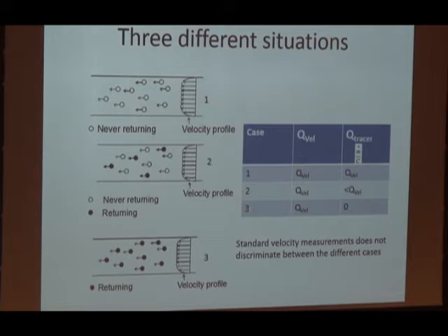If I then jump to the third case, when everything is coming back, then the tracer gas method gives an answer that the flow rate is 0. Because everything is coming back, how much gas I inject is fixed, but the concentration increases, so it becomes infinite, and then the flow rate becomes 0.